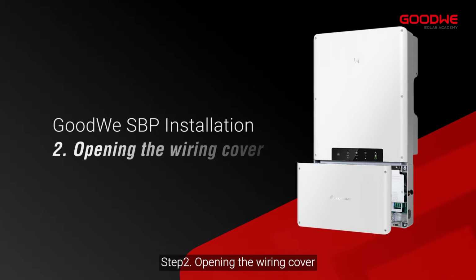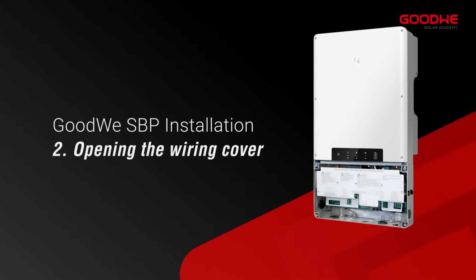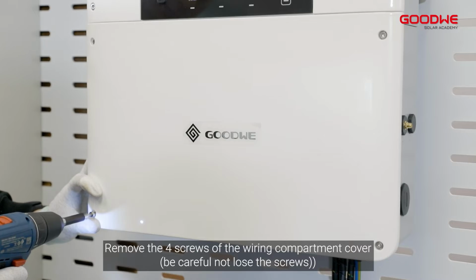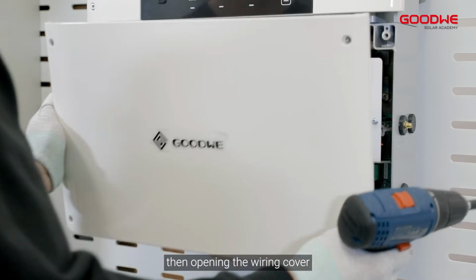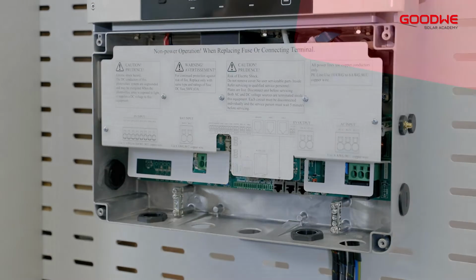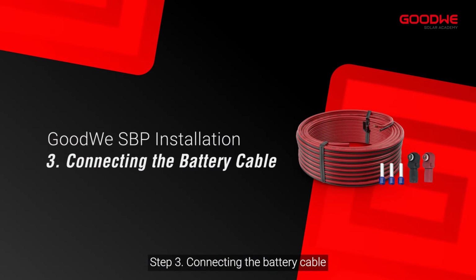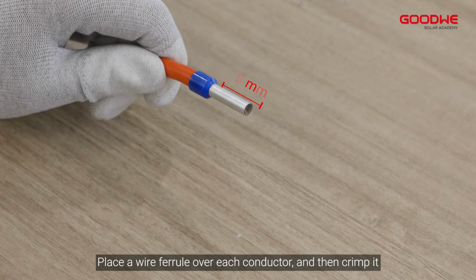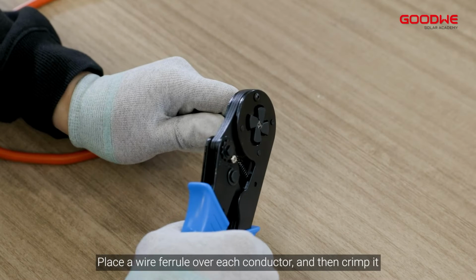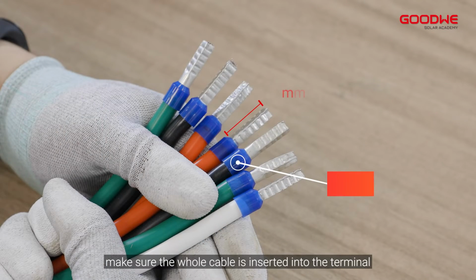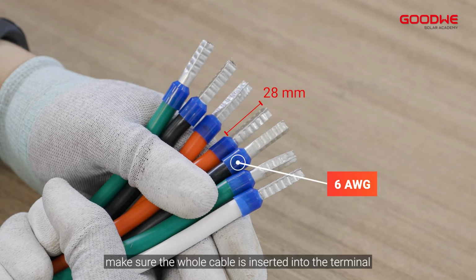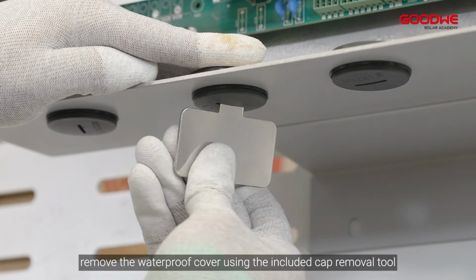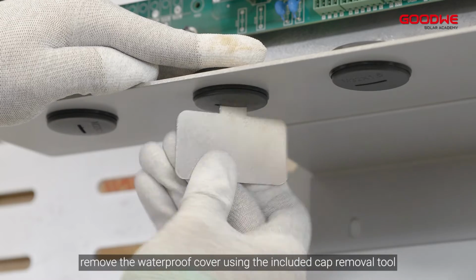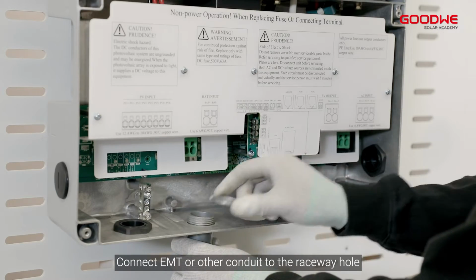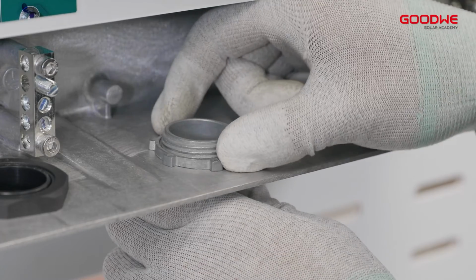Step 2. Opening the wiring cover. Remove the 4 screws of the wiring compartment cover. Then open the wiring cover. Step 3. Connecting the battery cable. Place a wire ferrule over each conductor, and then crimp it. Make sure the whole cable is inserted into the terminal. Remove the waterproof cover using the included cap removal tool. Connect EMT or other conduit to the raceway hole.